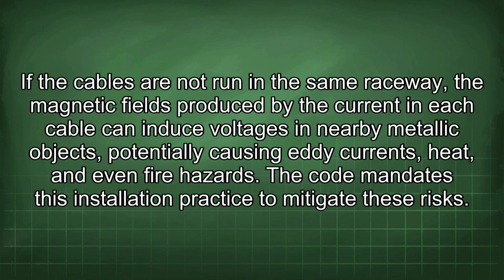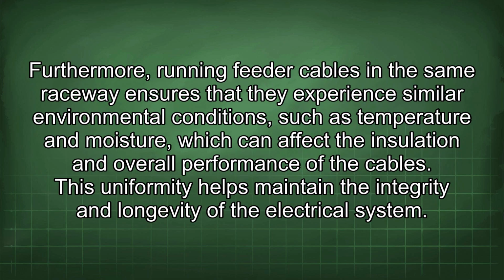If the cables are not run in the same raceway, the magnetic fields produced by the current in each cable can induce voltages in nearby metallic objects, potentially causing eddy currents, heat, and even fire hazards. The code mandates this installation practice to mitigate these risks. Furthermore, running feeder cables in the same raceway ensures that they experience similar environmental conditions such as temperature and moisture, which can affect the insulation and overall performance of the cables. This uniformity helps maintain the integrity and longevity of the electrical system.